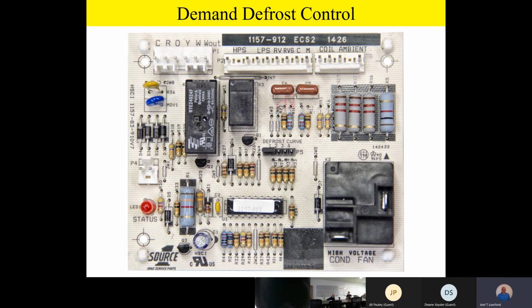Now, these are some basic principles with every defrost control. Whenever the unit goes into defrost, a couple things are going to happen. Number one, it's going to switch the reversing valve to the cooling mode of operation. So we're going to put the unit in cooling mode. The outdoor fan's going to shut off. And then we're going to have an output from what we call W out on the board, which we'll talk a little bit more about later.